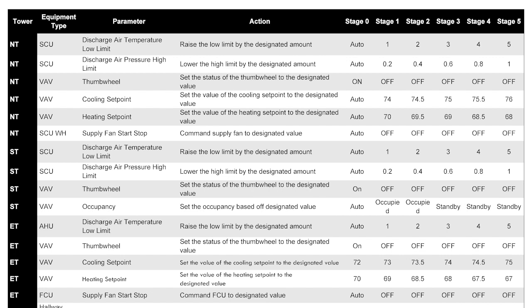And you can see with each stage and what those set points were, we didn't want to do it too drastic where it was going to cause a bunch of complaints, but we wanted to do it just enough where it was reducing that mechanical cooling load, reducing that mechanical heating load, reducing those fan speeds, cutting off the non-critical equipment. So a little bit more about the measures.